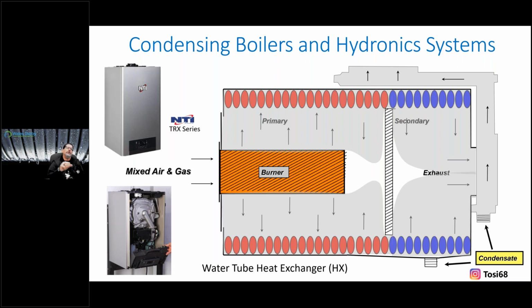So you can see, as we get a signal, a call for heat, something in the building, a domestic call, an indirect, that burner could be engaging from maybe a high fire, because it is a priority. We want everything we've got to go into that water to satisfy maybe a shower or someone with high demand on domestic, or we only have a couple of zones, or the house is now calling, but it's 35 out and not 10 degrees out. So we have the ability to modulate from a high to a low, or a low to a high, off of that burner. And this is the process in which we take advantage of that onboard software and the computer, and what we do to set it up.